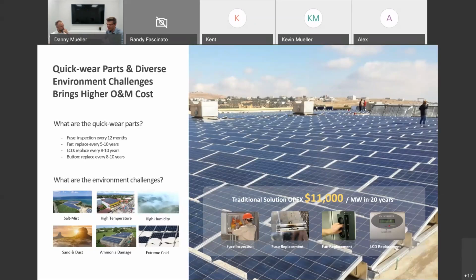Same applies to displays, buttons, and all those things. It's nice to have, when you install an inverter, to have a display that you can see, a nice diagram and all the grid code and the power it's producing. But honestly speaking, in a commercial rooftop, you place the inverter, you install it, and there's no one really walking to the inverter and looking at the display in real operation in year 5 or year 10. It just has to work, and that's it. So removing that part, removing the cost, and removing the possibility of that being a failure point really is a great feature to optimize, and focusing it on what's most important for an inverter.